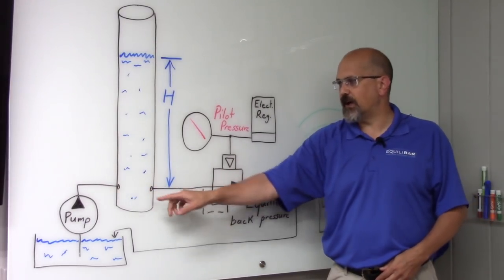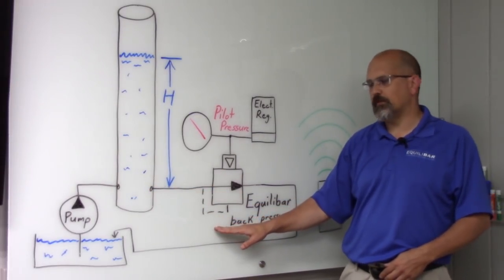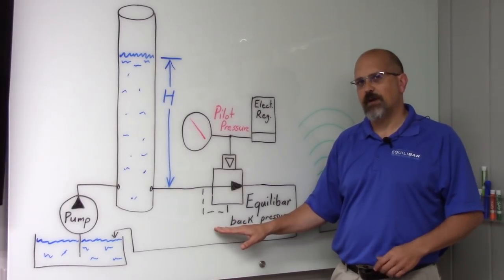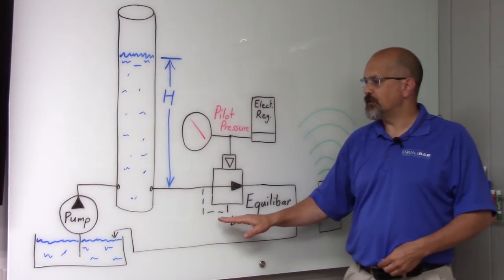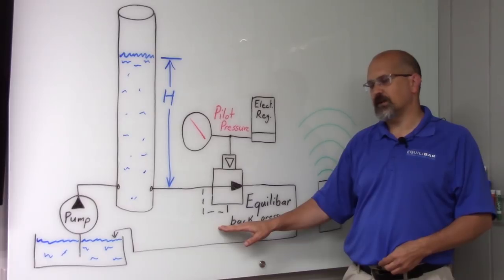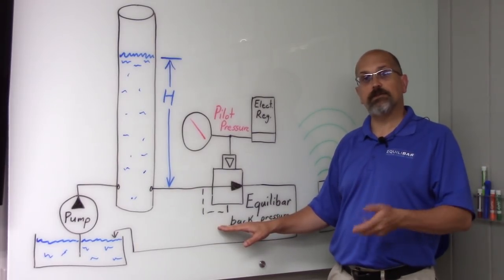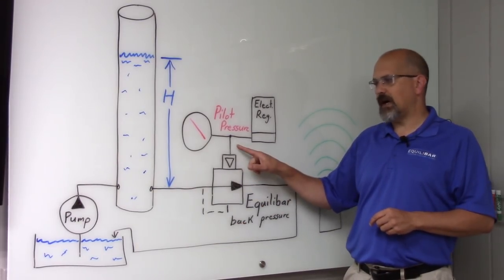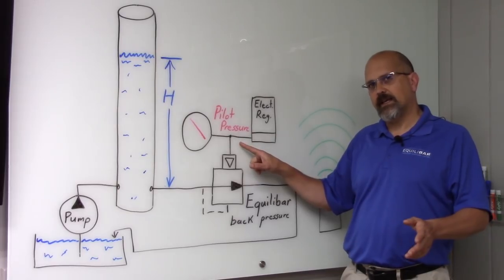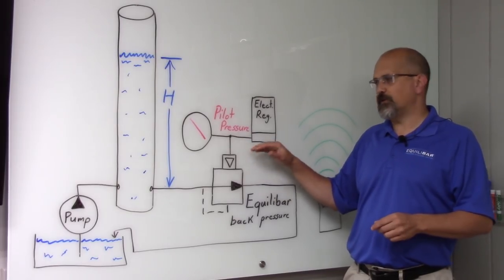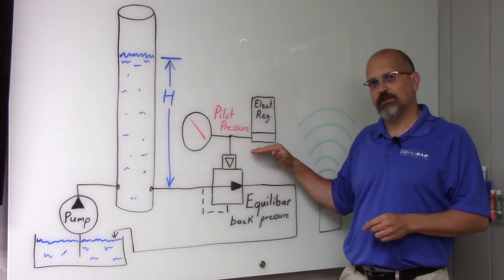The pressure in that column is going to be controlled by the Equilibar high resolution back pressure regulator. The Equilibar high resolution back pressure regulator receives its command or set point from an air pilot signal, and in the case of the demo, that air pilot signal is going to be coming from an electronic pressure regulator.